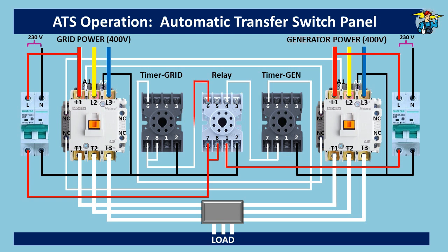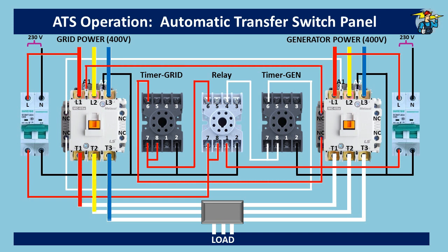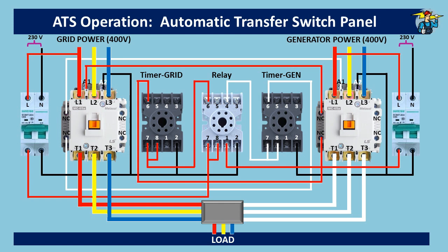At the same time, since the relay now has power, port 6 gets power through common port 8. This powers the grid timer, and after the set delay time, port 6 allows power to A1 of the grid contactor, restoring three-phase power to the load through grid power. The only thing needed now is to go and stop the generator manually.